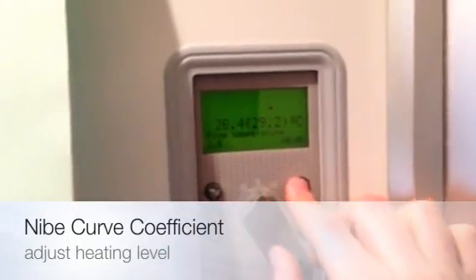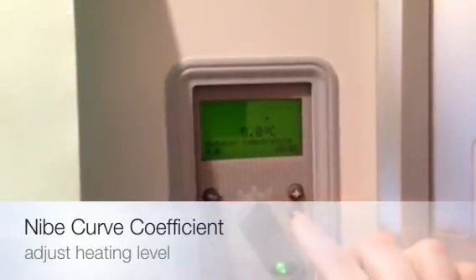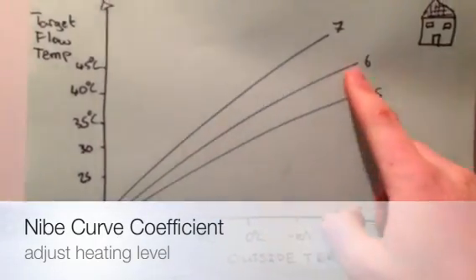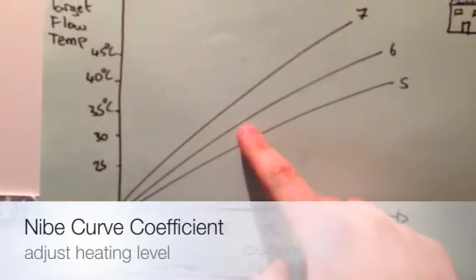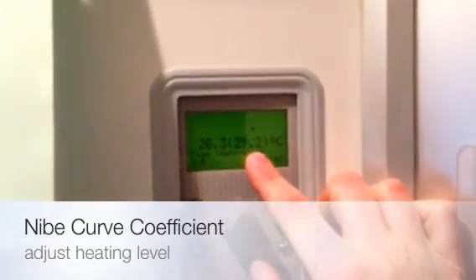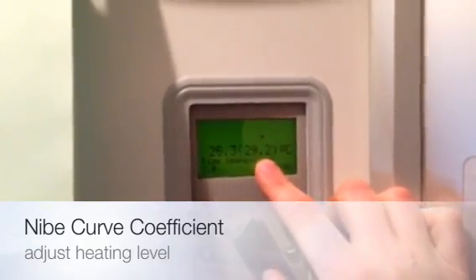We're on curve coefficient 6, it's roughly 8 degrees outside. Therefore, we're looking for somewhere just underneath 30 degrees to go into the building. And that's what we have here in the brackets. It's our target temperature to go into the floors.